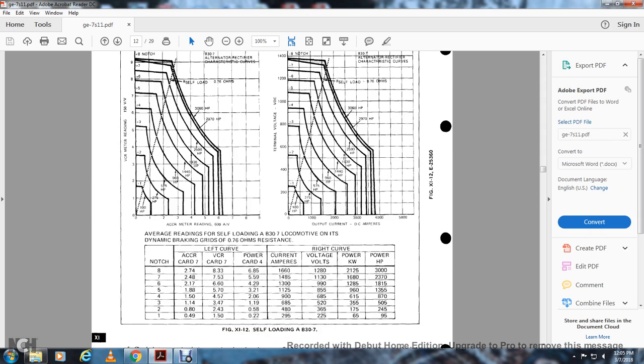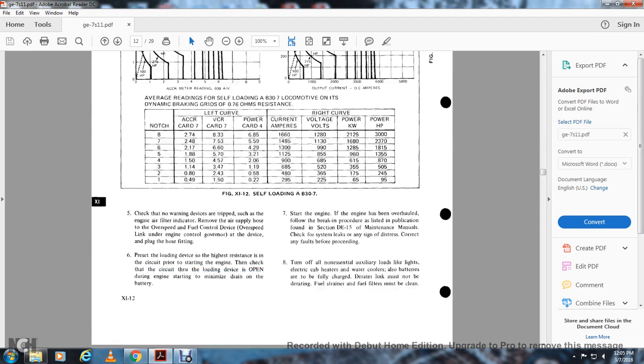Average readings for self-loading B30-7 locomotive dynamic braking grids is 0.76 ohms resistance. Notch 8 through 1, ACCR card 7, VCR card 7, power card 4. Left curve, right curve, current amperes, voltage volts, power kilowatts, power horsepower.